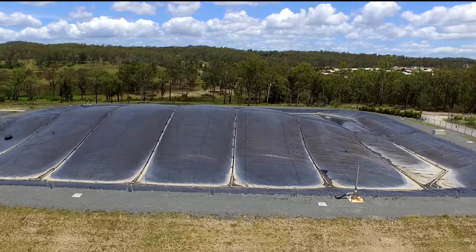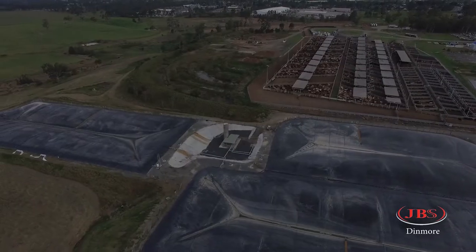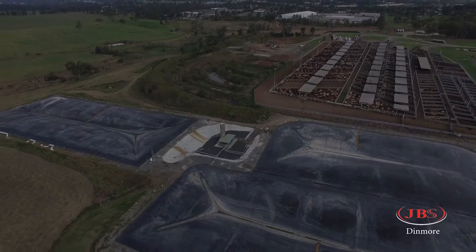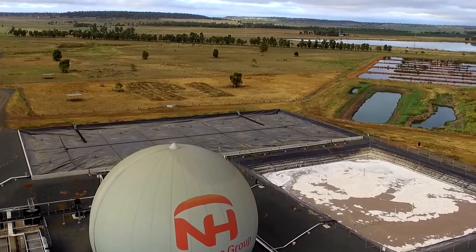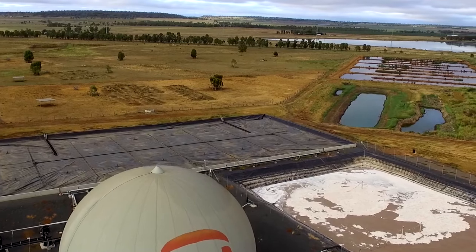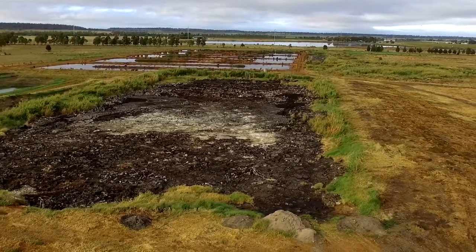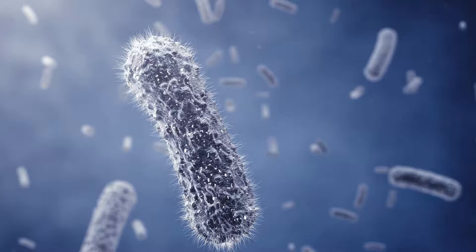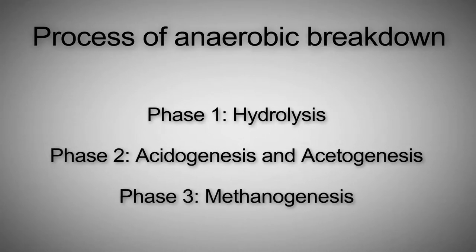Anaerobic ponds play an important role in the treatment of meat processing wastewater. Their key function is to reduce the level of organic contaminants and, to a lesser extent, oil and grease in large volumes of wastewater. They have little effect on the removal of nutrients such as nitrogen and phosphorus or on pathogen numbers. Anaerobic ponds are living ecosystems that contain a complex mix of bacteria that break down organic substances in the wastewater from meat processing plants. This occurs in a three stage process.